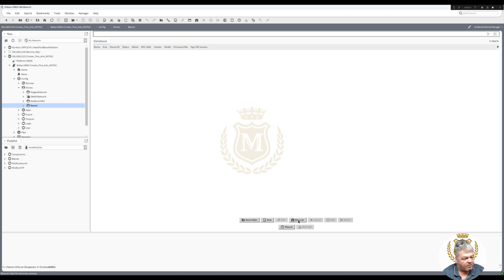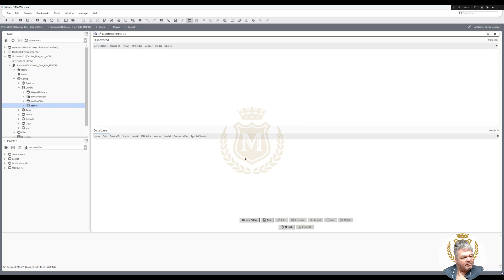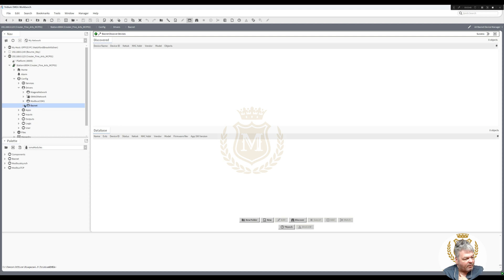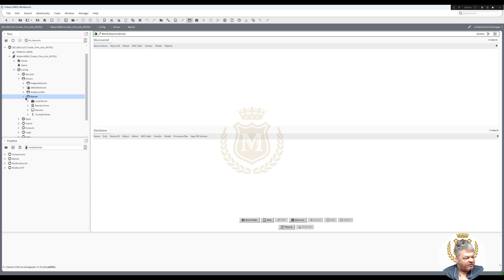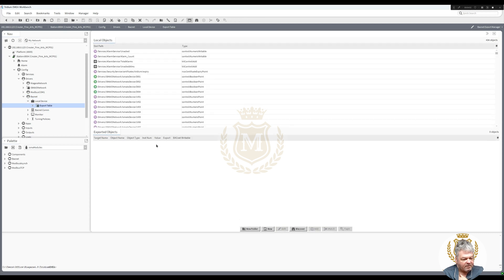If I go to Discover Points, this is from the station out. There may be one station on my office network, but looks like there's nothing. We're not discovering anyway — what we want to do is expose points. Open up BACnet, open up Local Device, and see the Export Table here. Double-click that, and do a Discover for all your points on your station.